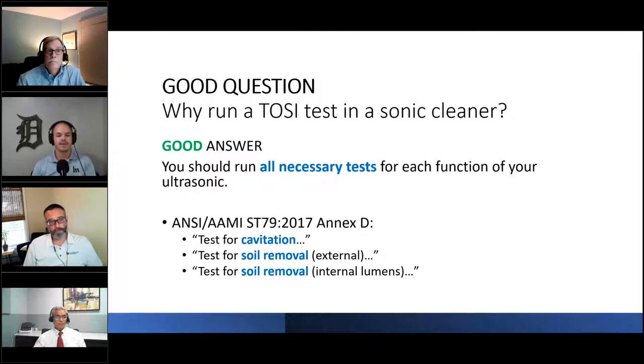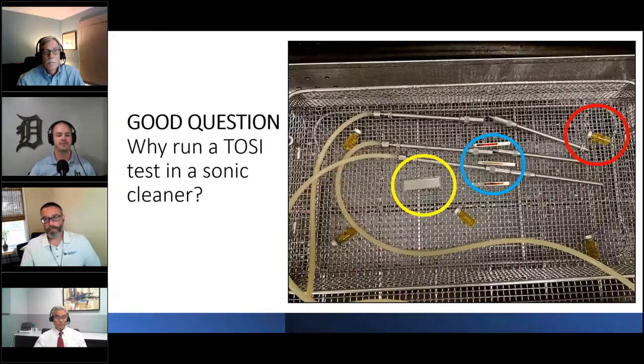So remember, that better answer to this question is that you should run all necessary tests for each function of your ultrasonic. Some ultrasonics actually perform thermal disinfection, so in all honesty, if you're running your ultrasonic cleaner to also thermally disinfect, you probably should be checking the temperature of that ultrasonic bath water as well. But let's move on to the next slide and we'll get a better picture of what this really means in real life.